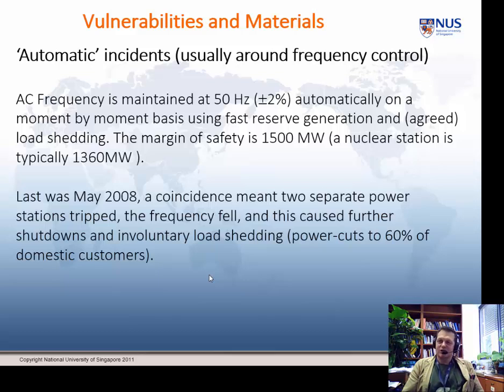52 hertz, it's fine. If it goes to 48 hertz, it's fine. And this frequency is maintained moment by moment using fast reserve generation, typically fuel cells. There's a whole list. You could use pumped storage, basically to make sure that sudden demand doesn't drop the frequency below 48.